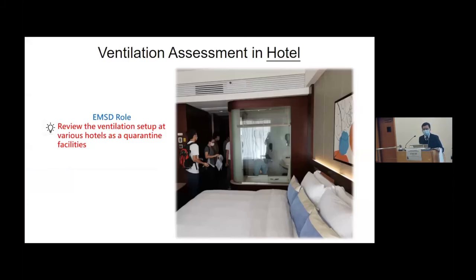As we all know, Hong Kong is an international hub with many travelers coming in and out on a regular basis. Although the number has significantly decreased since the time of the pandemic, there are still a number of travelers that would carry on with business in Hong Kong. With the mandatory quarantine measures in place, the government looked into the possibility of using hotels as quarantine facilities. EMSD was tasked to review the ventilation setup at various hotels and to provide advice from a ventilation perspective. In order to lower the risk of the hotel staff being infected by guests quarantined inside guest rooms, an airflow from corridor to guest room was required. Sampling tests were carried out on site to check the airflow pattern.